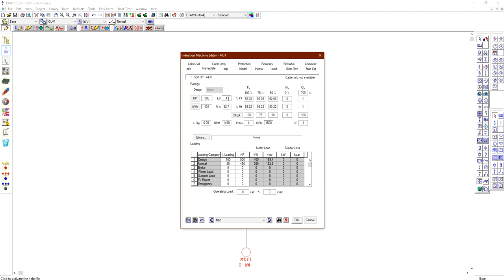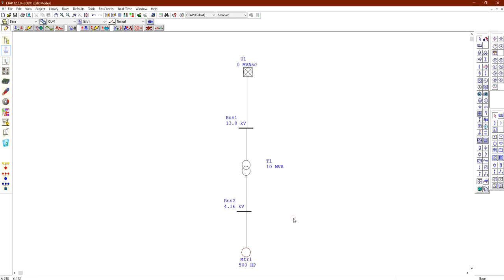As an example, we will set the motor to 500 horsepower. Click the kilowatt field and tick to convert to horsepower, then type 500. The program automatically retrieves values from its NEMA library, providing power factor, efficiency, full load current, operating voltage, kilovolt-amperes, slip, and RPM. Click OK to confirm.